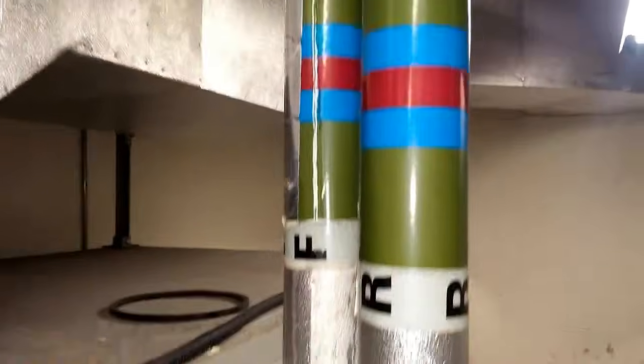This is a heating coil, and we can just see there the flow coming down here, entering into the coil, and again you can see just how thin these coils are. You can see a few dents there as well. This is being damaged slightly during the maintenance. You can see the coils coming through there as well.